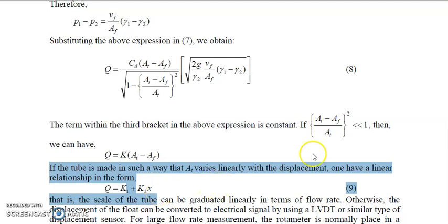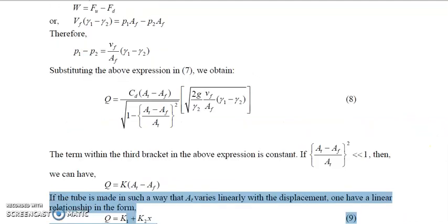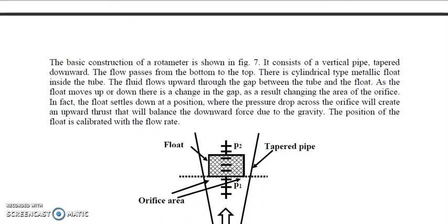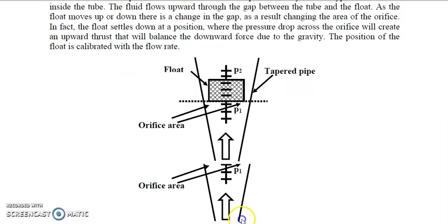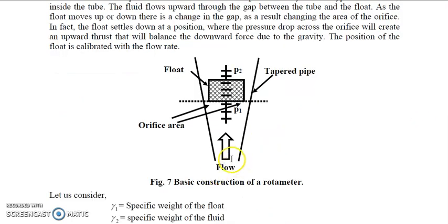So actually if you watch the diagram of rotameter, whenever we are measuring the flow, we start the flow of liquid and the float moves in the upward direction, and due to the formula derivation and its designing consideration, the observer only watches the displacement of the float on this vertical scale, which is linearly spaced.